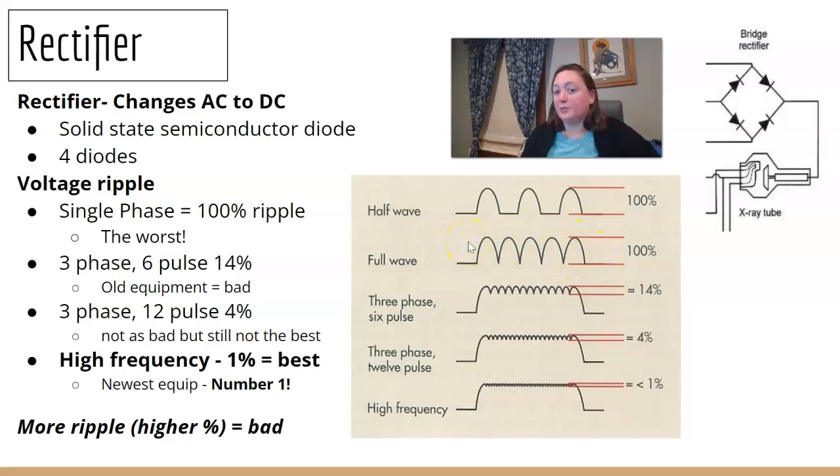As your equipment has improved over time, we started with single phase equipment. And then we went to three phase with a six pulse. So we had more pulses involved. Then we went three phase, 12 pulse. Again, more pulses, less drop. Your newest, and I think all the equipment you're working on, is high frequency equipment. There's something here that's called voltage ripple. And that's how much it has to drop back down before coming back up. So how much drop in between. So single phase has 100% ripple. Because it has to go all the way back down to zero and then back up again. And it's bad. So 100% is bad.